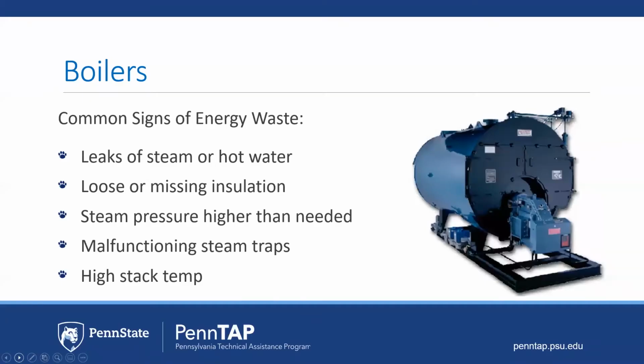Boilers. Common signs for energy waste associated specifically with boilers. You could have leaks of steam or hot water in your system, loose or missing pieces of insulation along your piping. Your steam pressure might be too high. You could have malfunctioning steam traps, which is a very common issue, or a high stack temperature. Tackling any of these will help you make your system more efficient in the long run and have savings, cash savings.